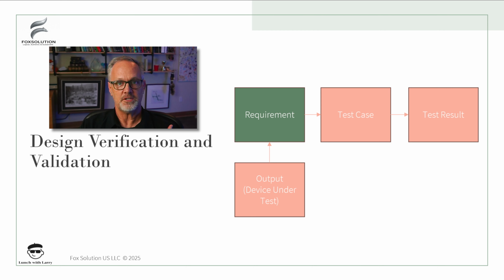And then, of course, we want this traceability from the requirement to the output, because the output is the device under test. When we run reporting, we want to know not only do we have a good test result, but what it is that was tested and the revision level of what was tested, so that we can provide this traceability across not only through the design inputs, but also into the outputs, so that we can get the full breadth of the design control. Okay, so we'll talk about that in more detail as well. But this is a very important part of getting out of the system what we want, this evidence that we comply with our definition of good.